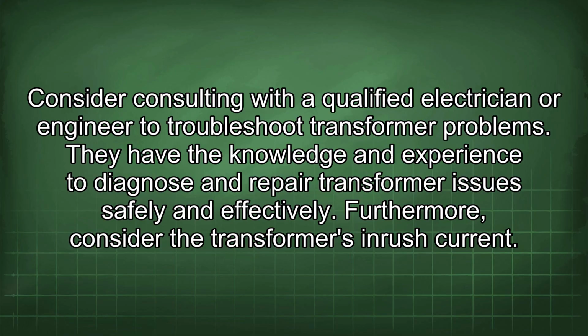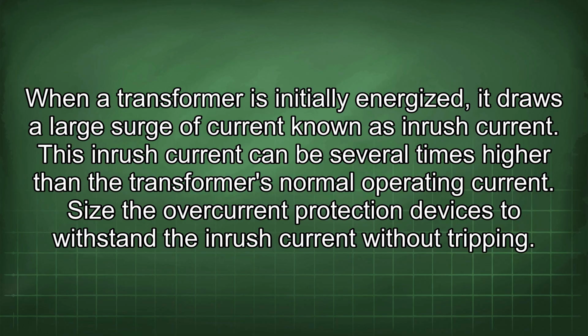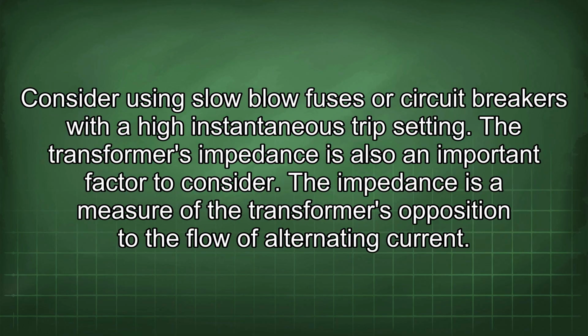Furthermore, consider the transformer's inrush current. When a transformer is initially energized, it draws a large surge of current known as inrush current. This inrush current can be several times higher than the transformer's normal operating current. Size the overcurrent protection devices to withstand the inrush current without tripping. Consider using slow-blow fuses or circuit breakers with a high instantaneous trip setting.